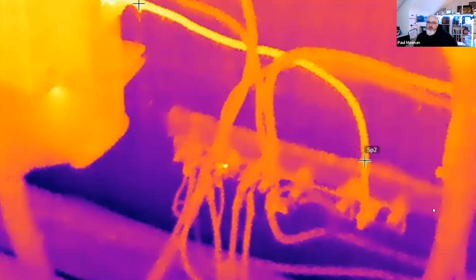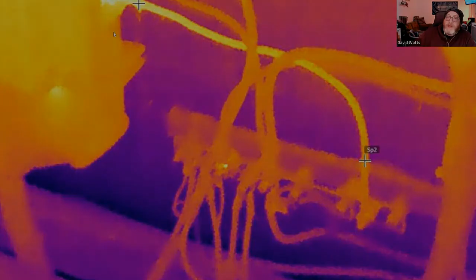A lot of the earthing is quite well sized, especially on things like rail, so you'll have some current on them, but it doesn't always mean you'll see them on thermal. You have the benefit of having the clamp meter with it, but in this case, there's no clamp meter necessary. It was evident there was energy on that earth, and we could actually see an increase, a bit of joule heating toward the connection with the actual DNO cutout there.